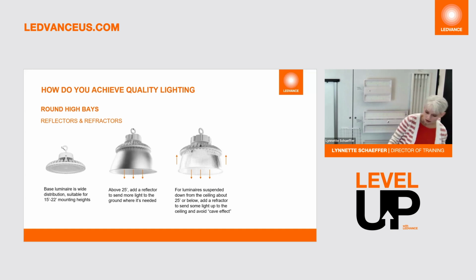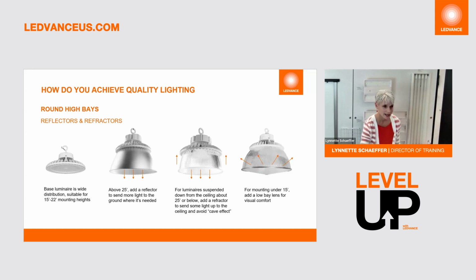All right, and then of course, if you wanted to, you could always add a lens. Just keep in mind, if you do add a lens, you are going to reduce your lumen output, but it will really help with visual comfort. So just be aware of that. And of course, you can add that to either a reflector or a refractor if you choose to. So again, in summary, a reflector reflects the light and pushes it downward, while a refractor is typically clear. It's meant to push the light outward and also upward and also a little bit downward too.